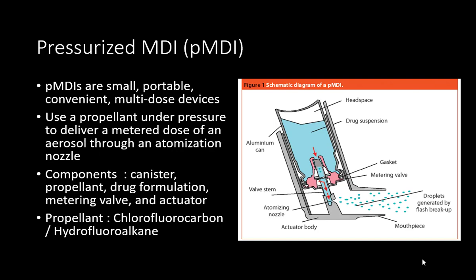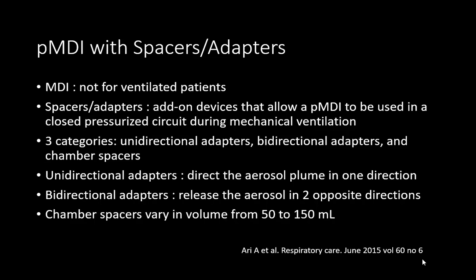The problem with this is, per se you cannot use it in a ventilator patient. If you disconnect the patient, put on ventilator and give salbutamol, it's not going to work. So you need spacers or adapters which can be used along with the ventilator circuit in line. Okay, so there are basically 3 types of these: unidirectional, bidirectional, based on whether the flow is going to be in one direction or 2 directions, and the chamber volume varies from 50 to 150 ml.